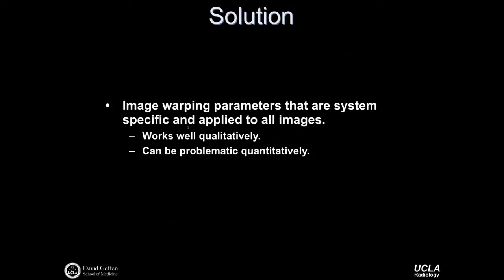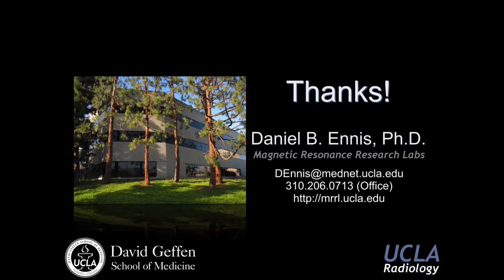The solution is image warping parameters that are system-specific and applied to all images. This works well qualitatively, correcting overall anatomy and geometric fidelity, but could be problematic for more quantitative approaches if care is not taken in how MR signals are handled. That was a brief discussion of several artifacts that occur in MR imaging — there's a rich history of many possible artifacts, but this at least gets you started.